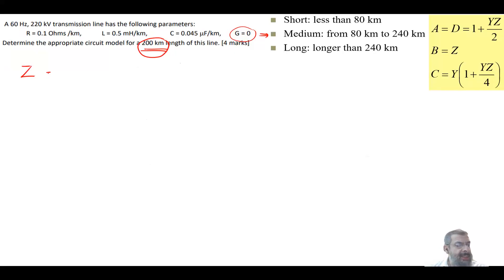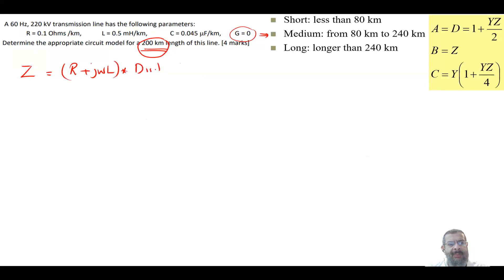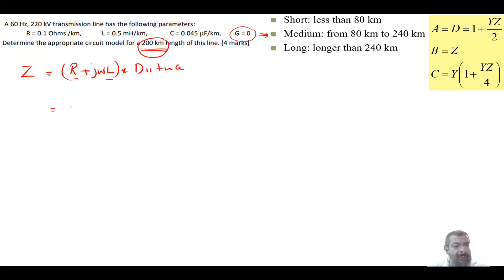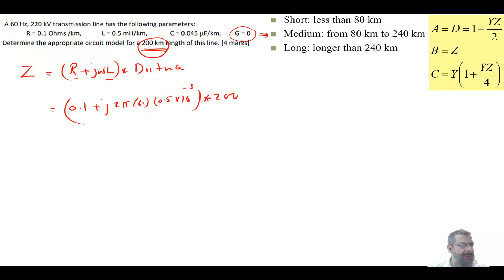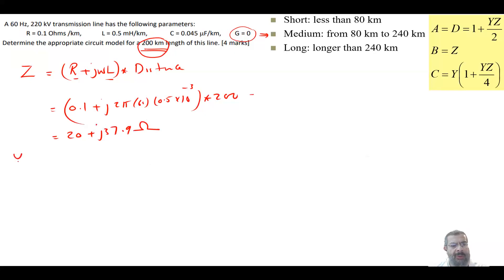Z equals (R + jωL) times the distance. Since the values are per unit length, we multiply by the length to get ohms. This is equal to 0.1 + j·2π·60 × 0.5×10⁻³, all times 200 km, which gives Z = 20 + j37.9 ohms.